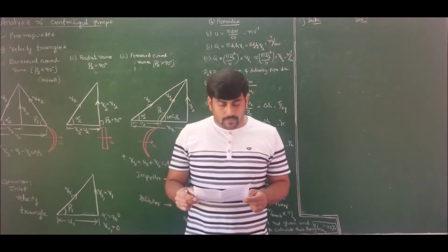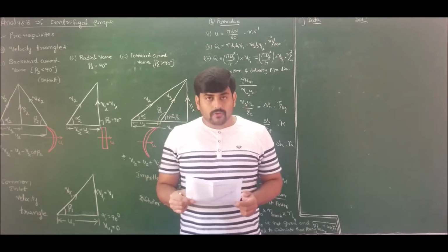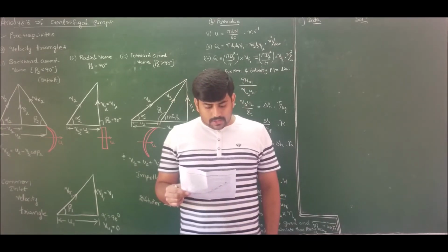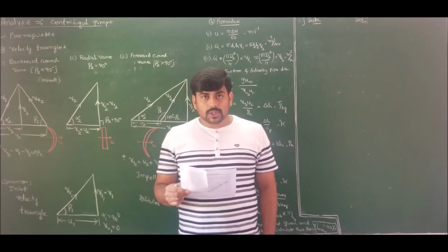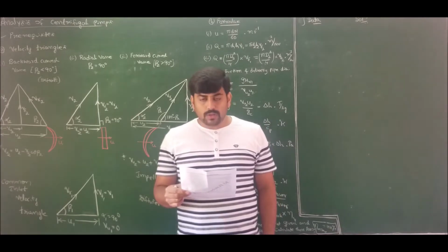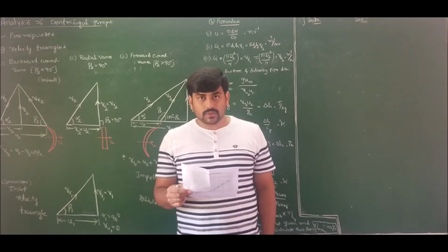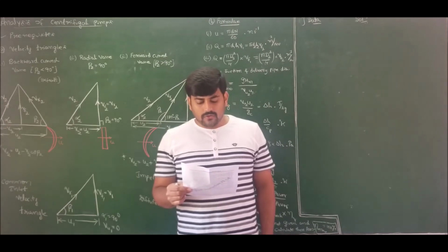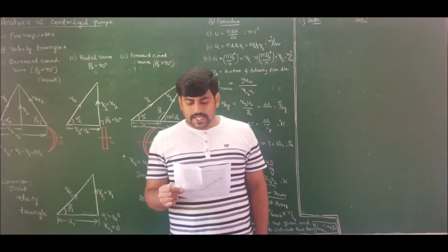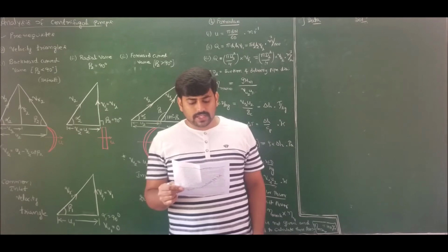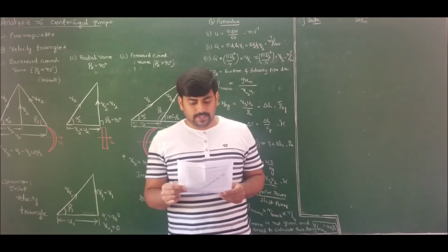Now moving to problem number 4. Problem number 4 states that a centrifugal pump with 1.2 meter diameter runs at 200 rpm and pumps 1.88 meter cube per second. The average lift being 6 meters. The angle which the vane makes at exit with the tangent of the impeller is 26 degrees and the radial velocity of flow is 2.5 meters per second. Find the manometric efficiency and least speed to start the pumping if the inner diameter being 0.6 meters.